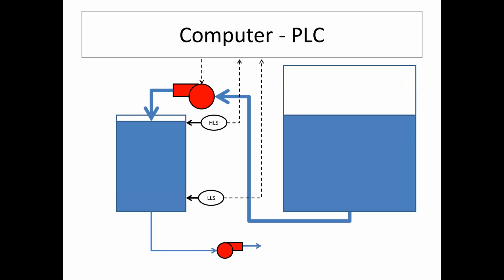And then when that high level switch gets hit, it sends a signal to the PLC, and the PLC shuts the pump off. Whereas in the first example, you required a great deal of operator observation and intervention. This method frees the operator up to do other things that are more applicable to their skills, so they don't need to sit there and babysit this process. This is completely automated. It doesn't take any operator observation at all.